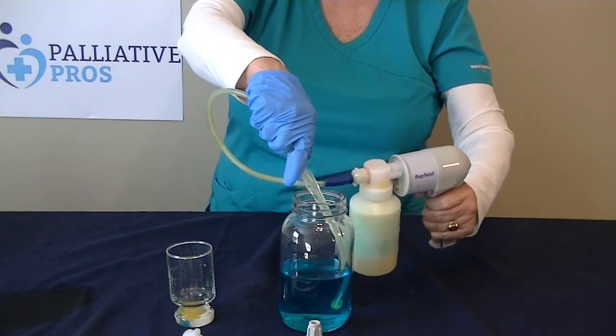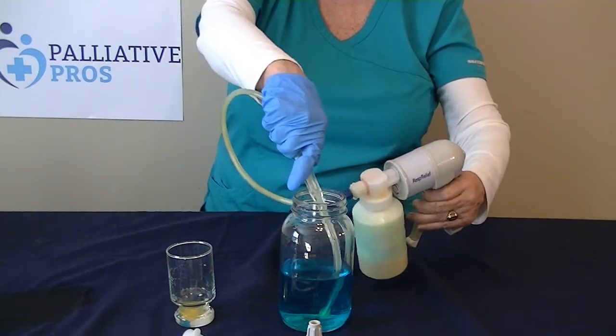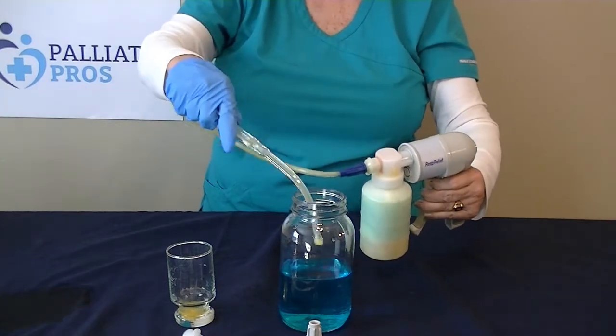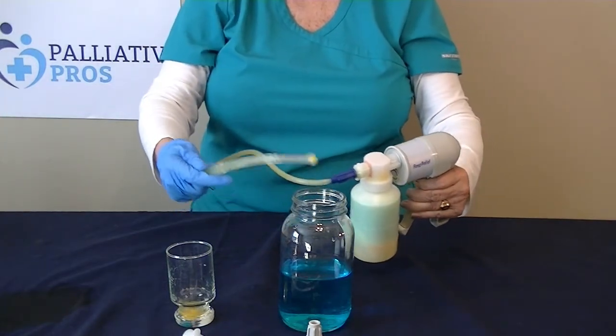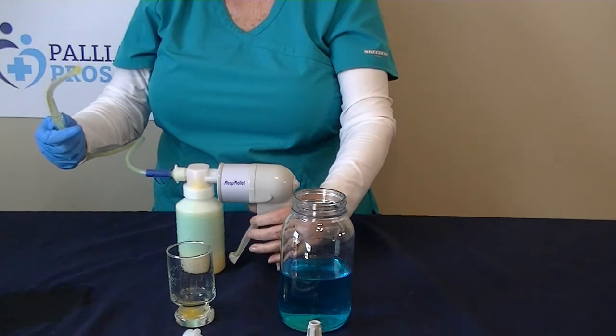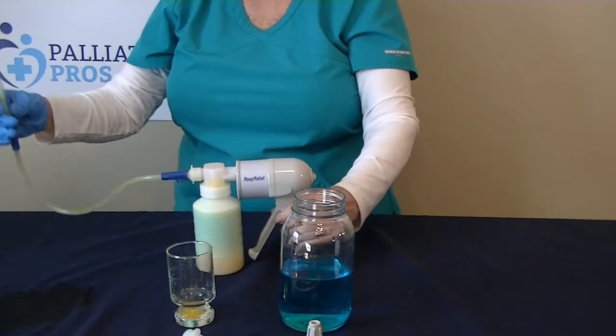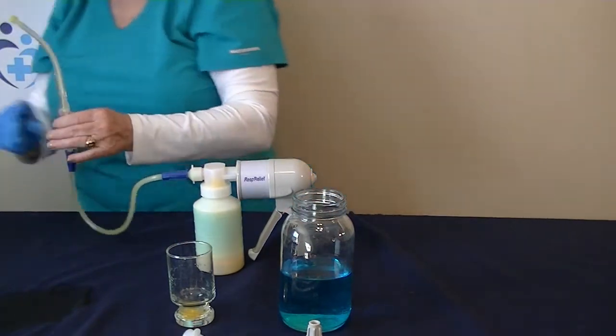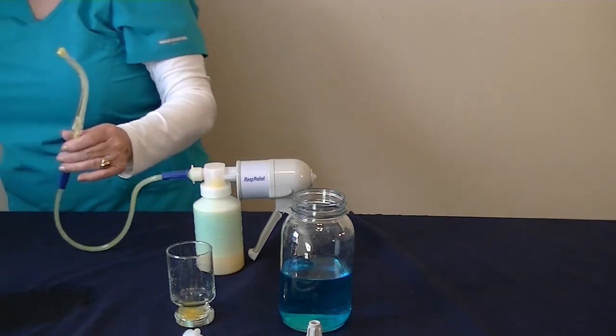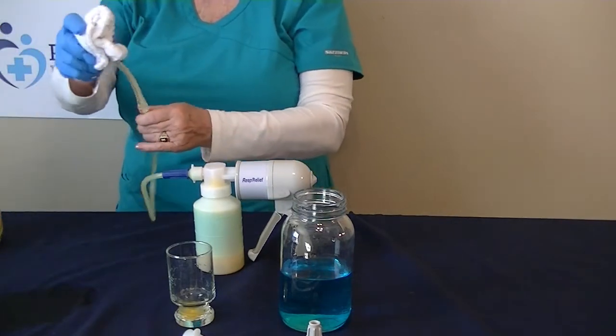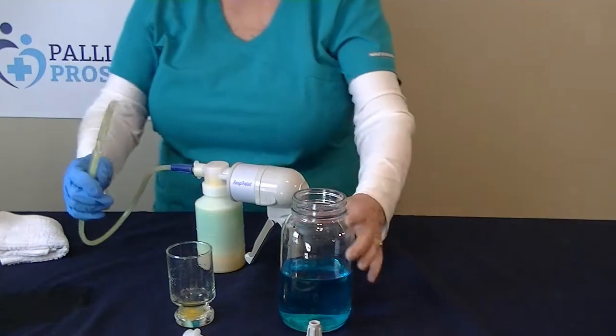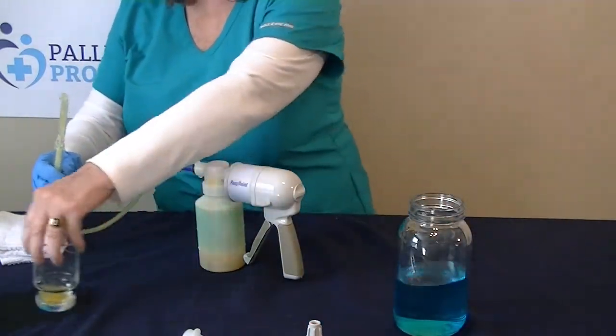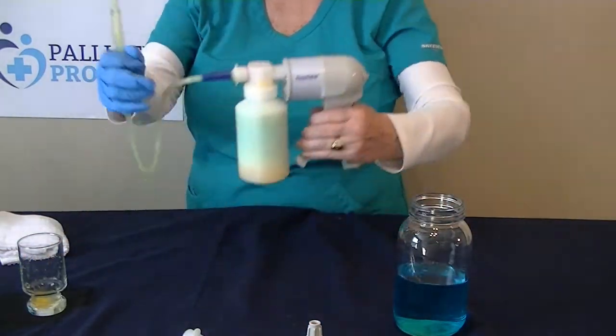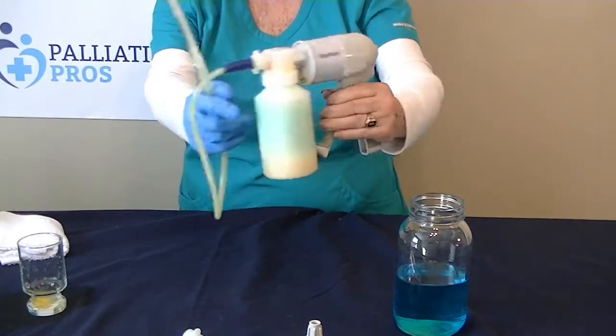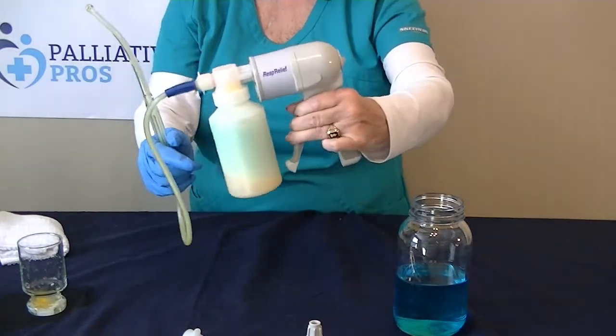Notice how whisper quiet the device is compared to the meat grinding sound of an electric suction machine. Release and repeat. The pump is uniquely designed to prevent backflow to the patient and leaking inside the unit. It is also equipped with an overflow protection mechanism which will engage, locking the trigger handle once the collection jar is full, so you can't overfill.